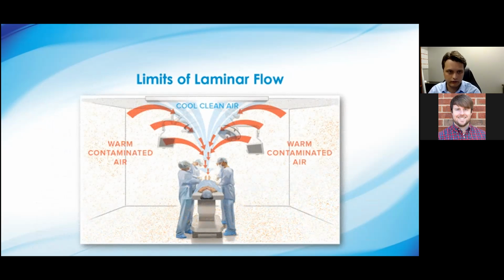Because the laminar flow is just a passive device smoothing the air out as it passes through, it may be laminar for the first couple inches out of the ceiling, but it quickly takes a dramatic and unexpected turn. What's happening here is that the air coming into the space is responsible for controlling the temperature of the space. There's a lot of heat, people, equipment generating heat in the space. So generally the air coming in needs to be about 10 to 12 degrees colder than the air already in the room. Because that air is so much colder, it's more dense than the warm air already in that room, and it gets acted upon by gravity and accelerates towards the ground.